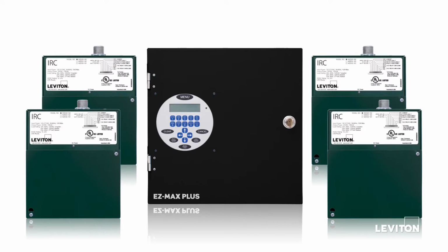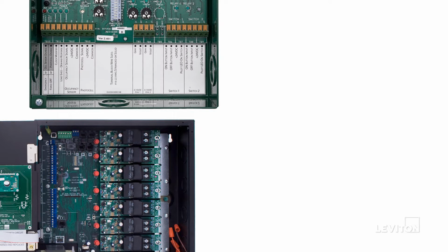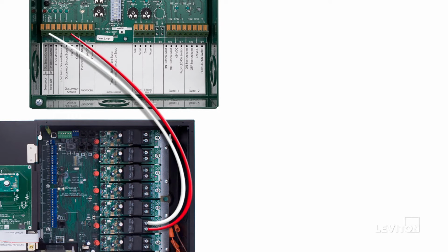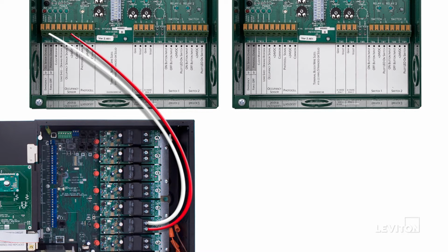Note, you can connect one contact closure or relay to multiple IRC units by following this procedure. Wire the contact closure or relay to the primary IRC unit as described in this video. Then, run 18 gauge wire from the wire landed on the terminal labeled force off in the primary IRC to the terminal labeled force off in each additional IRC.